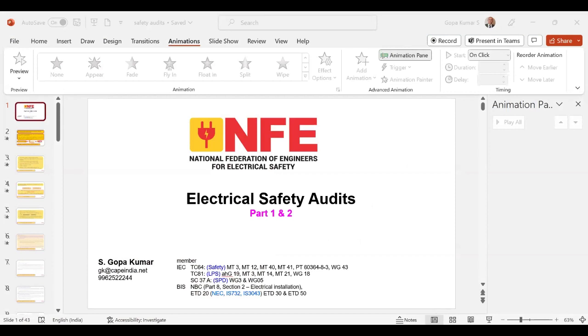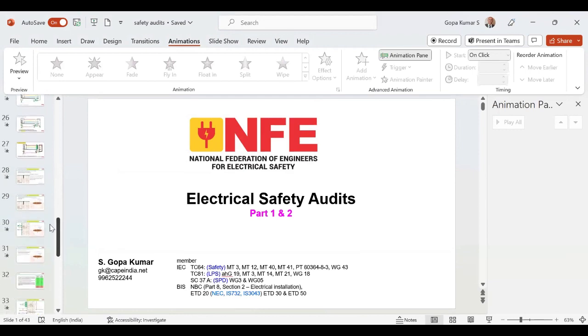I am searching for the words resistance area. In the definitions, you can see resistance area: the surface of ground on which a significant voltage gradient may exist. You can also find further explanations in IS 3043. I am skipping through some of the explanations. Similarly, in NEC, National Electrical Code of India, here also the 2011 version, you can find the resistance area. Now you see here the resistance area, voltage gradient. The earth electrode should not be installed in proximity to a metal fence, and all these requirements are there. Electrode resistance area. Once we talk about the earth electrode, we should have a clear understanding about the resistance area. Otherwise, we will end up with trouble. Coming back.